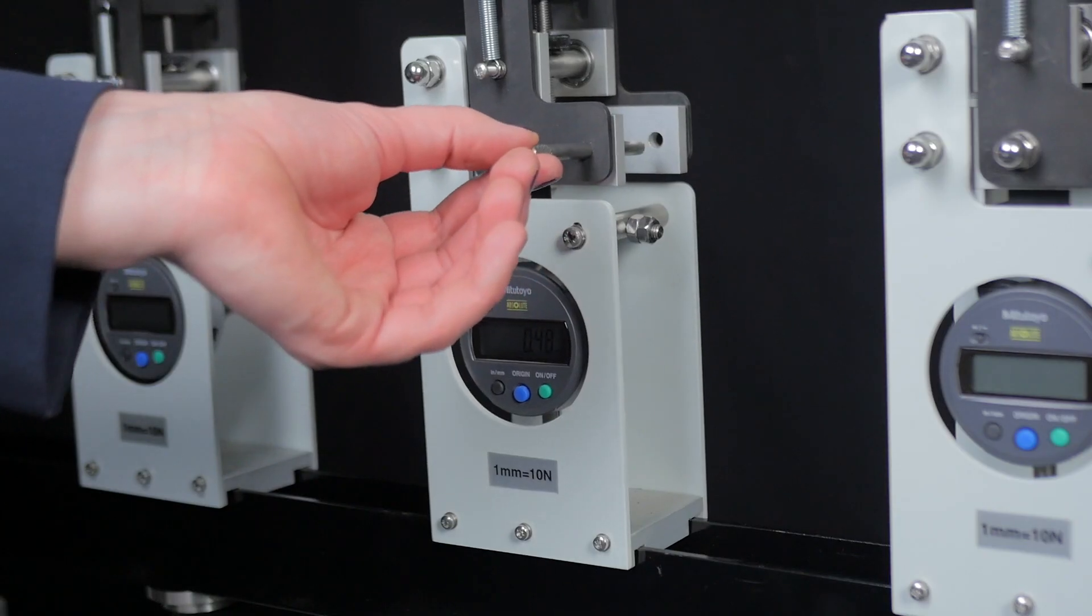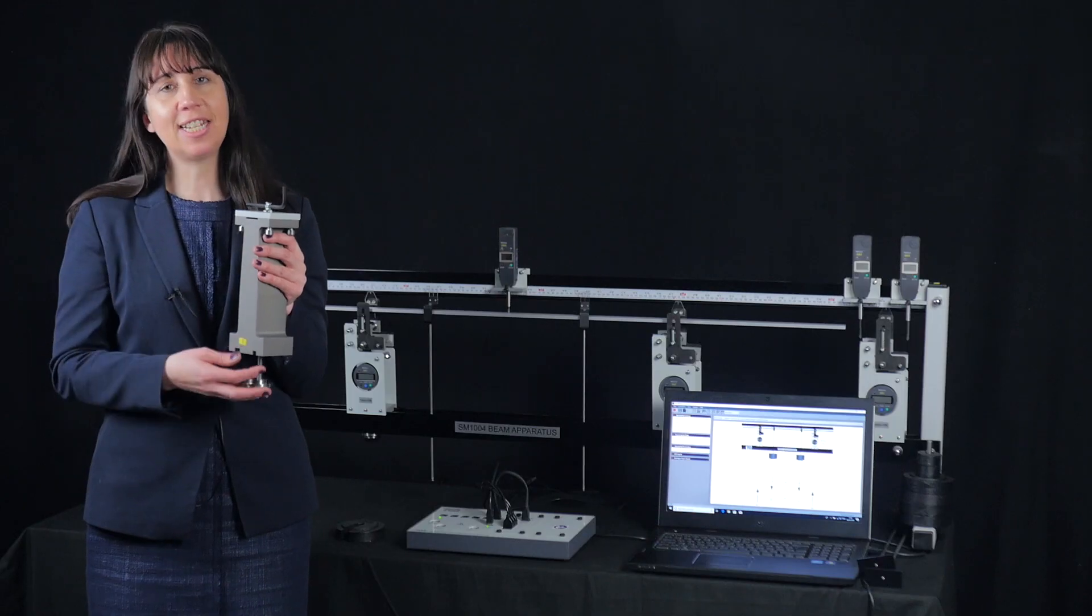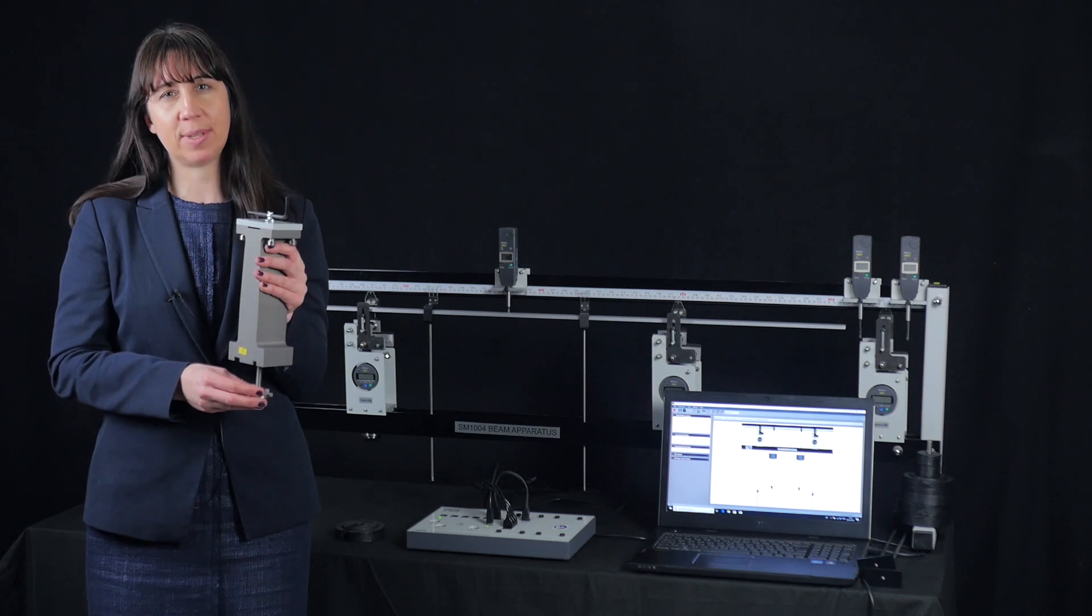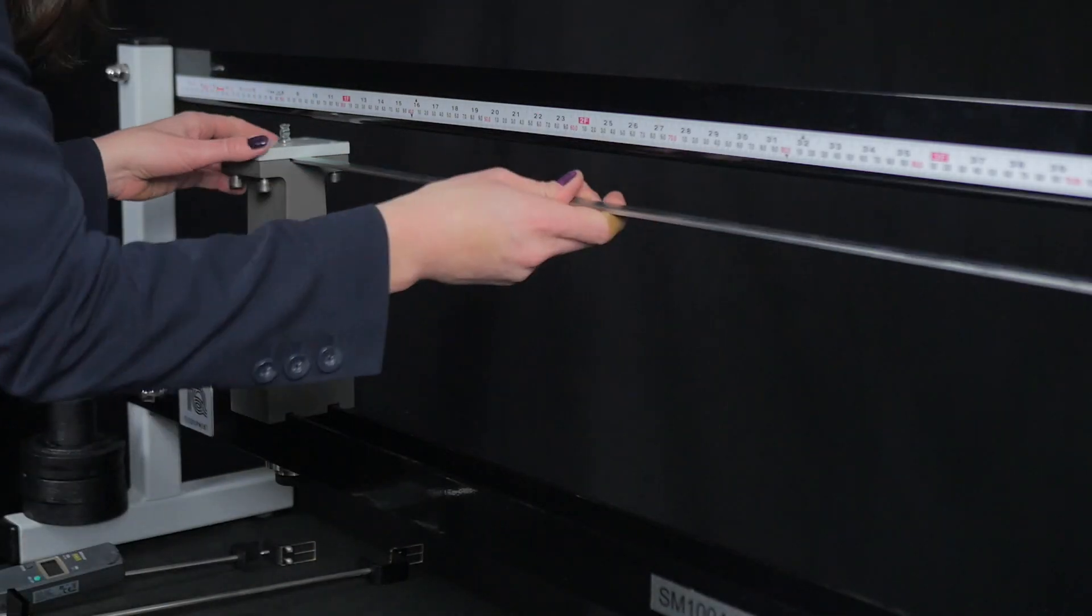The locking pins here convert the load cells into rigid support when required. The cantilever support here is a rigid pillar with a sturdy clamping arrangement to hold the beams when built-in end conditions are required.